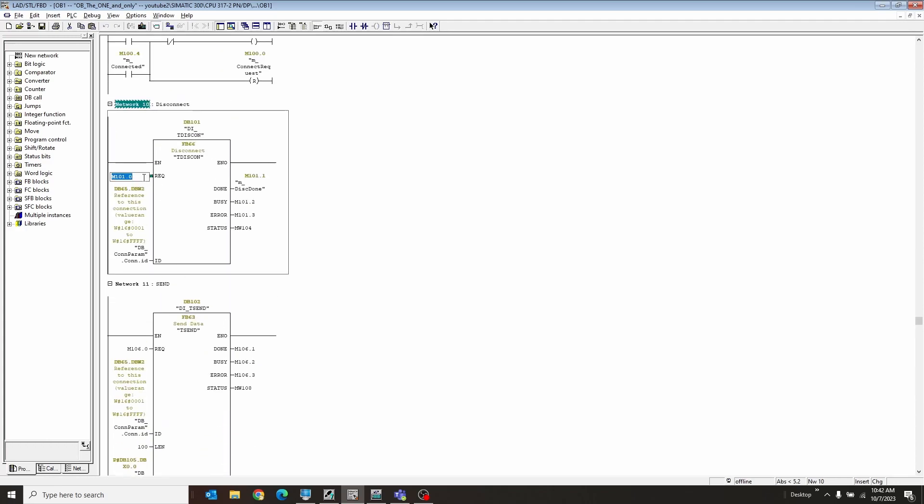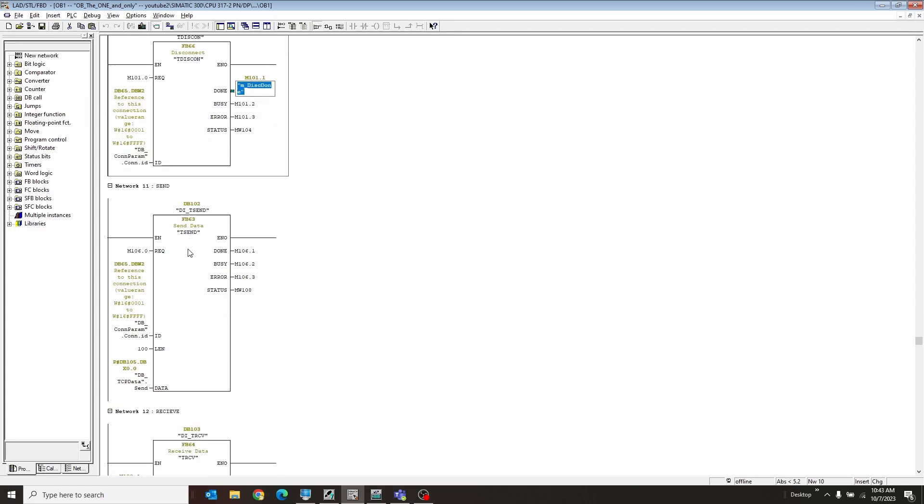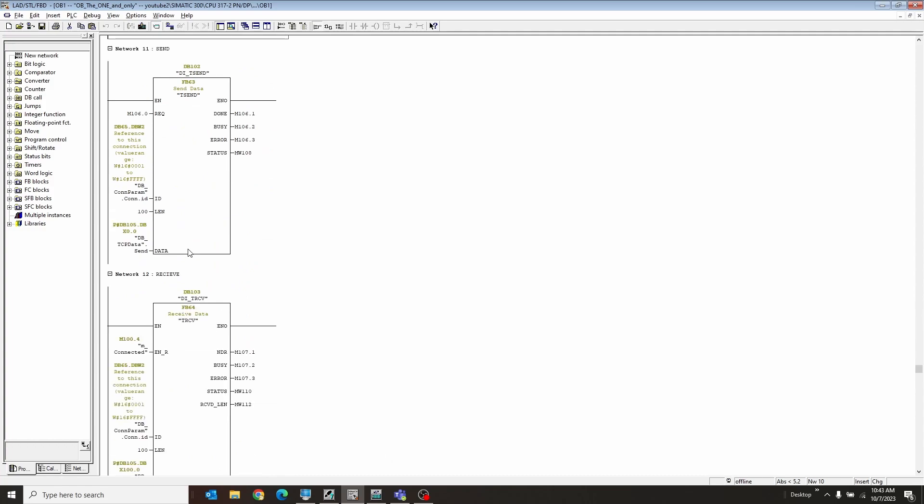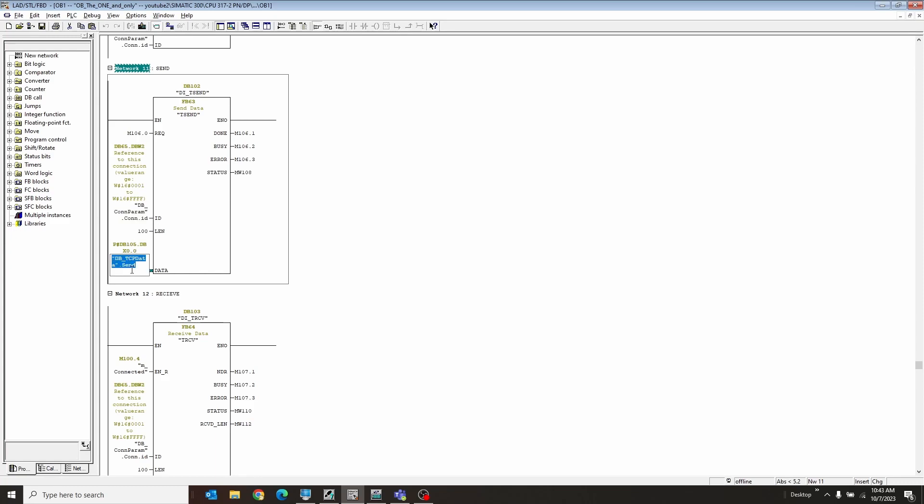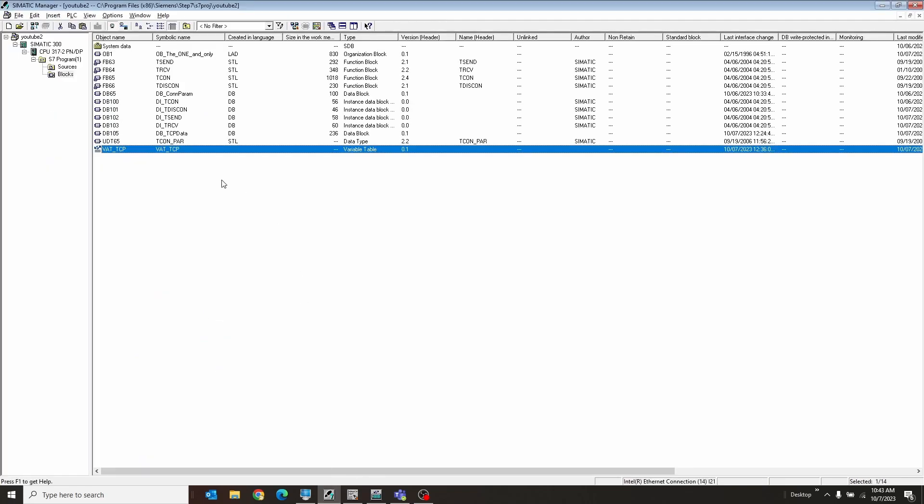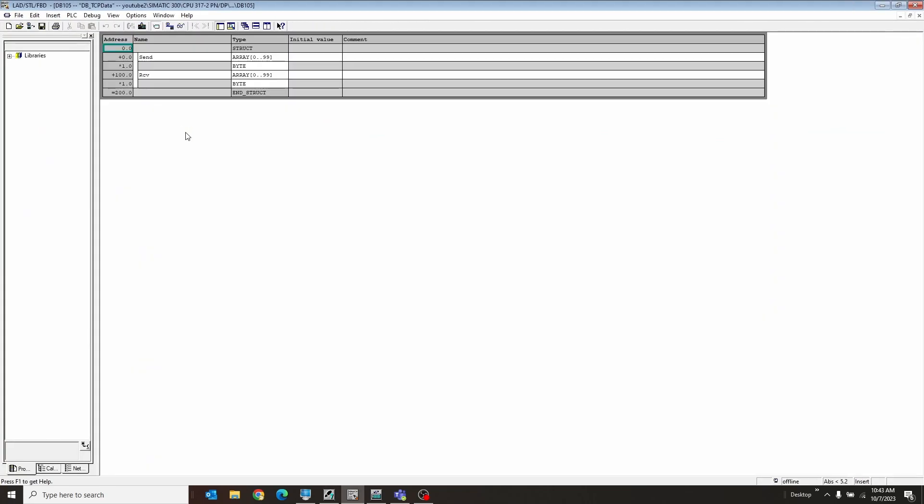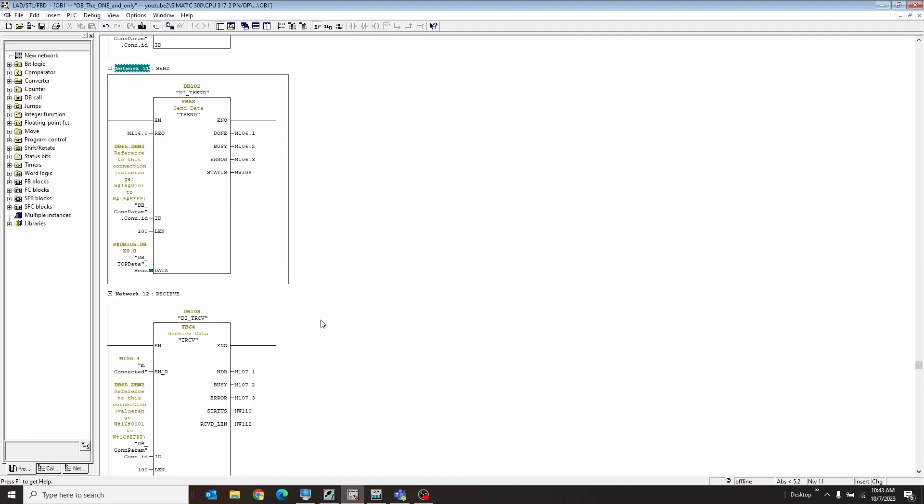So essentially, this is just the bit to request the disconnect. This is the ID specifically. In our case, it was hex of 20. And this is I'm done. And here's some more information in case it doesn't get done. The send is very similar. Here's the request to send. Here's the connection ID. Again, that hex of 20. We're sending 100 bytes. And this is from that DB for sending the data. So I'll just go ahead and show you here real quick. And all I have is a send of 100 bytes and receive of 100 bytes. And so here is his done, busy information.